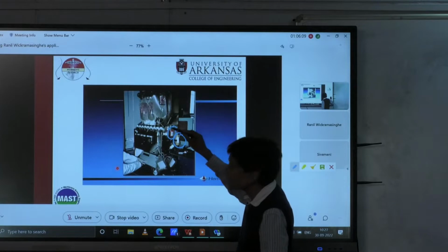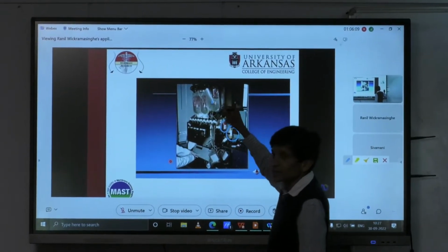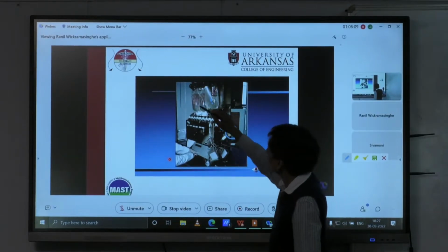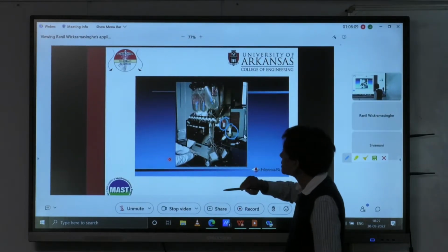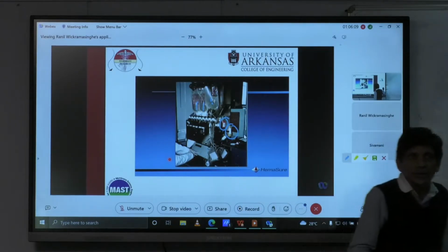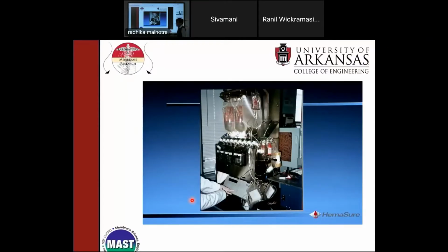This was a pre-filter. You needed to remove any aggregates. Here is our waste bag. So the waste, glycerol containing waste goes in here. Okay, this is our diluent. We also add something called adjuvants. At the very end of the process, you add these adjuvants, which basically helps preserve the red blood cells, okay. So it's like adjusting some of the salt species and so forth present.